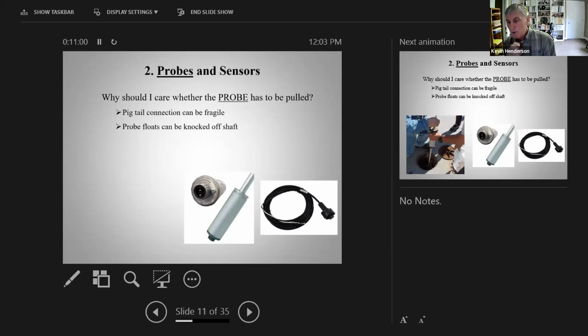Sometimes when you disconnect this little pigtail and you pull it out of the probe socket there, that little plastic will just crumble in your hands. And that's a very bad thing to happen, obviously. When that little plastic crumbles in the probe, there is no way to fix that other than buying a new probe. So that is the main reason we do not like to pull the probe unless we absolutely have to. The pigtail will also come apart on you sometimes, but that's relatively cheap. That's about $150, or it used to be. I'm not sure what they would cost today with inflation the way it is, but it used to be about $150 to get you a new pigtail. But the probe itself can be quite expensive, so we just don't like to do that unless we have to.